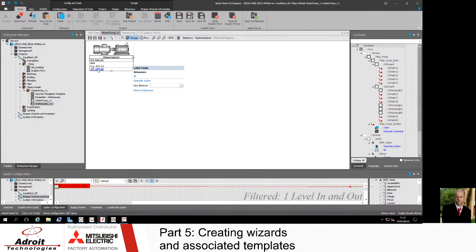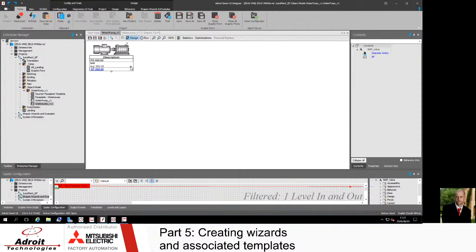You'll also note that I've used a blue foreground with an underline. I like to use that because a lot of people are used to clicking on links. In fact, you'll even see in our task label here, anything you can click on is blue with an underline. For anybody that's worked on web pages before, it's a good indication. It also helps my operators know what they can click on. It gives them something recognizable to click on. It's all part of the pattern recognition of our high performance specifications that I spoke about last week, or I believe the week before, maybe even.